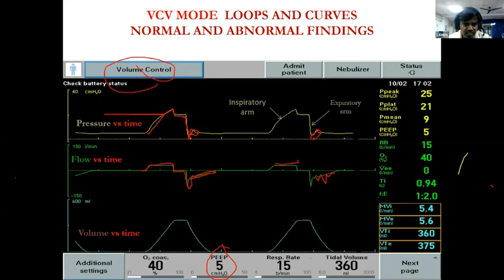The patient is completely on sedation. And this curve we can see here one by one. I'll show. See, in the pressure curve, the trigger is there. It may be like this, or it may be like this. When the patient initiates the breath, the curve will change like this. Understood? So in the flow curve, you can see inspiration and the expiration starts here. Usually the expiration should start from here, but here the expiration starts here.